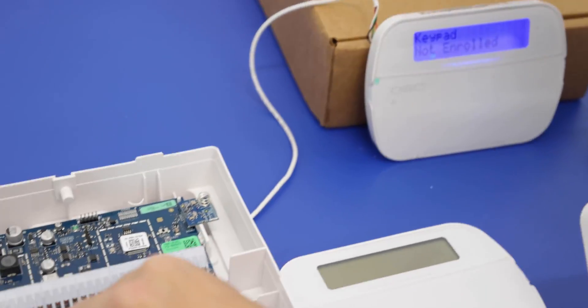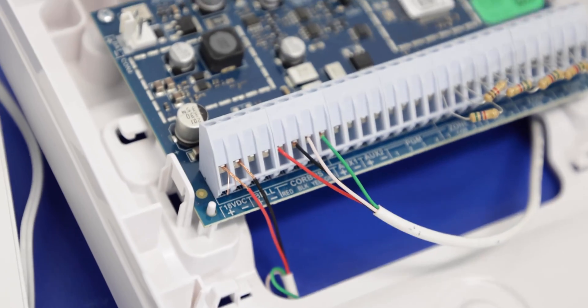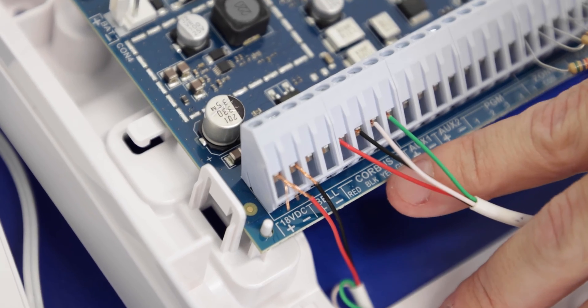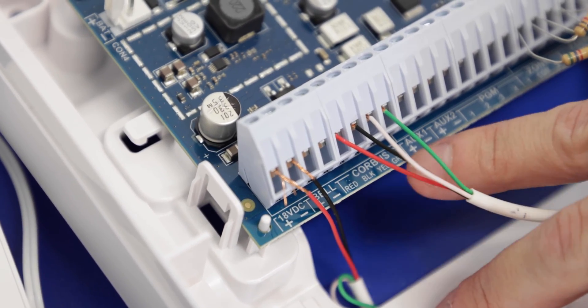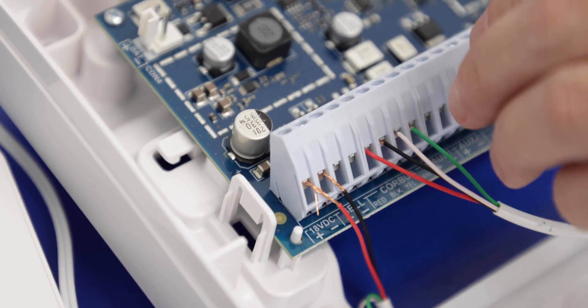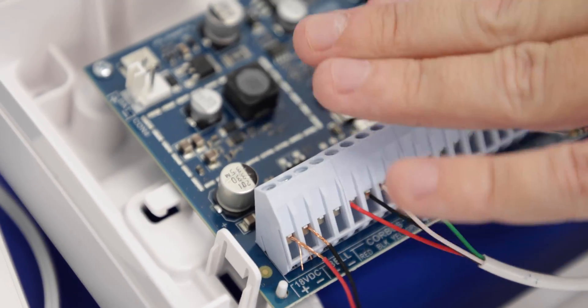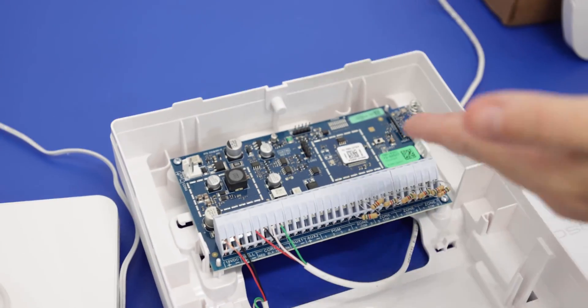Right over here on our wired-to-wireless converter, we attach that to the Corbus terminals. Again they made it pretty simple — red, black, yellow, green — so you're just going to match the wiring to this. The keypad is going to get its power directly from this converter as well. The converter itself has its power supply connected and that's all the power we need for this.